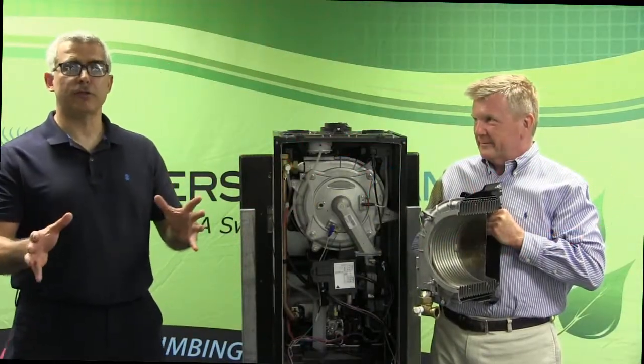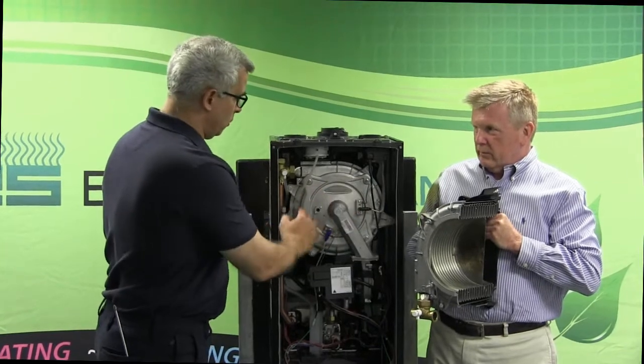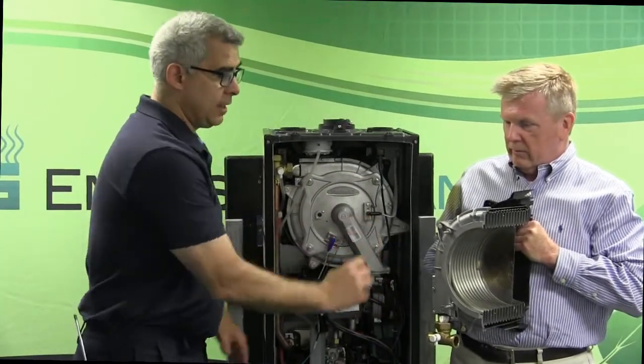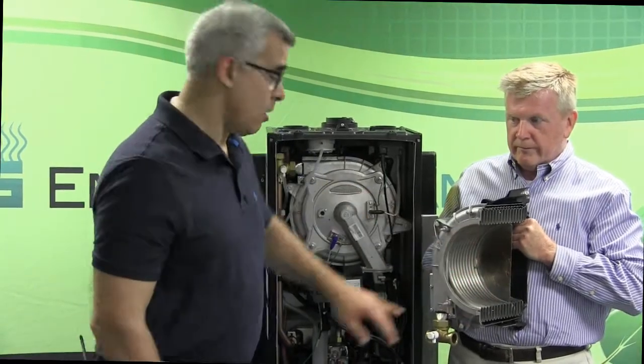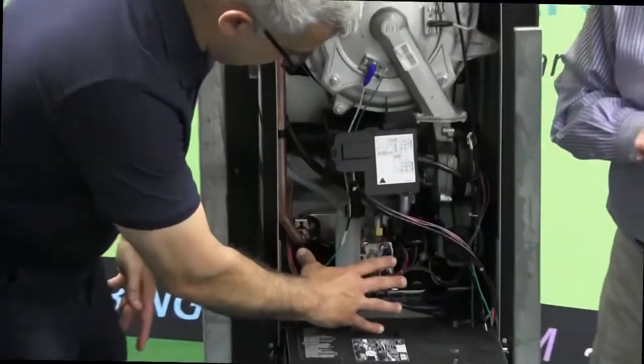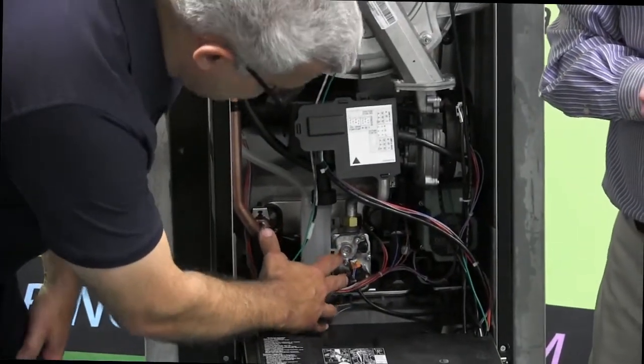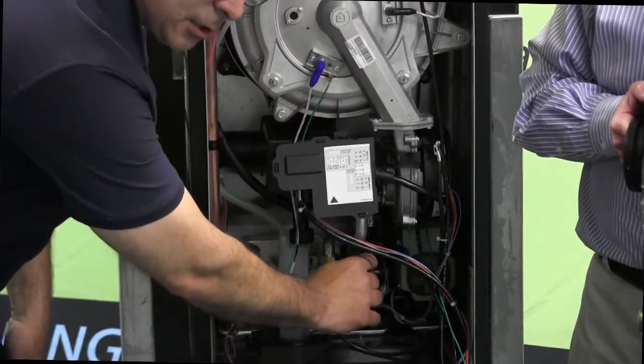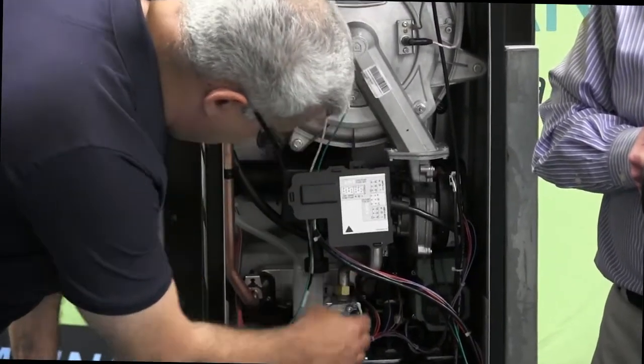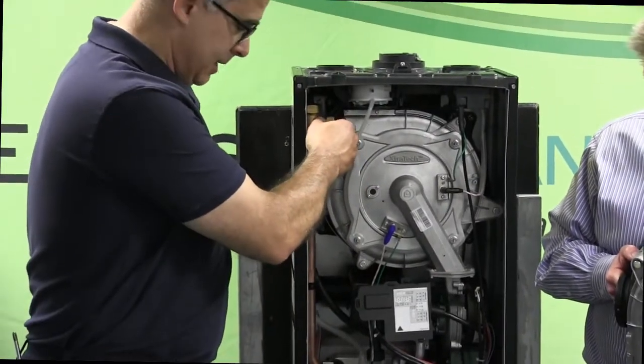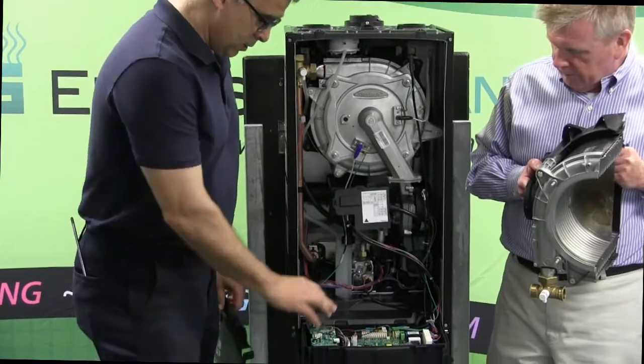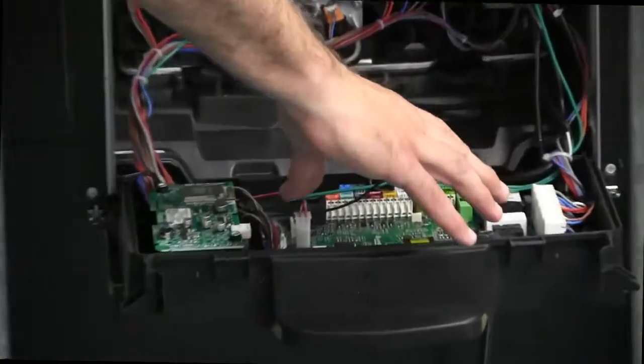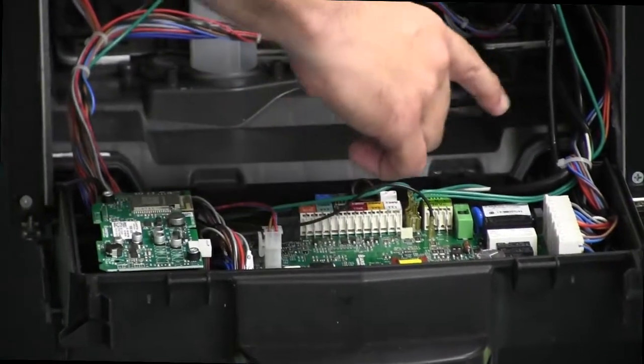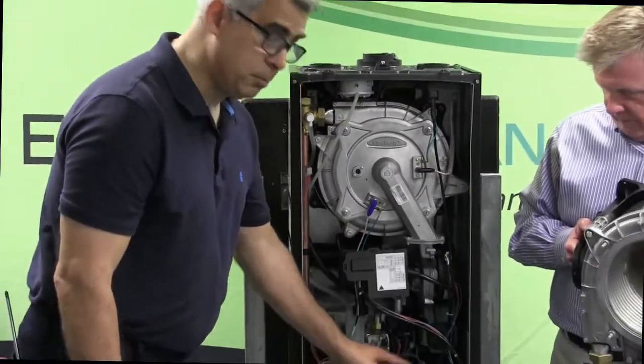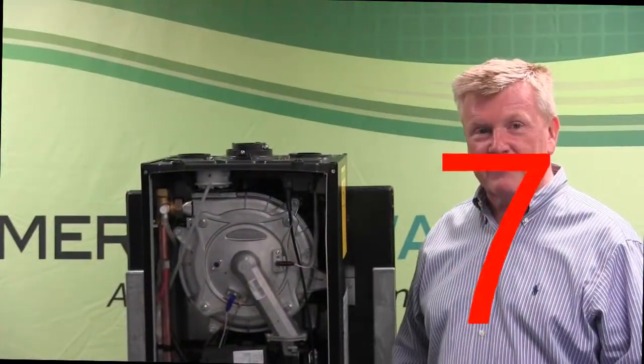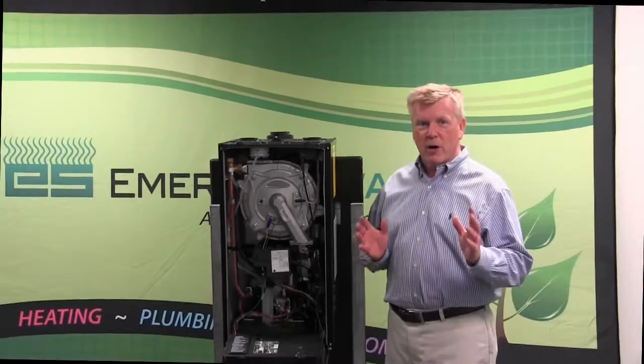Number 8, easy to service. The heat exchanger can come out with 4 bolts, disconnect the gas valve, and this pulls out, and it's easy access to clean the heat exchanger here. Also, at the bottom here is where a lot of the parts are. There's the gas valve that's easy to get to for adjustments. The pump's right here. There's an air pressure switch in the back there that we can adjust. There's a 3-way valve. And up here, we can purge it here easily. And as far as the electronics of it all, we have our Wi-Fi board right here. We have a connection board here with the low voltage connections and the line voltage connections. This particular unit has a plug, so it pretty much plugs right in the wall. Easy.